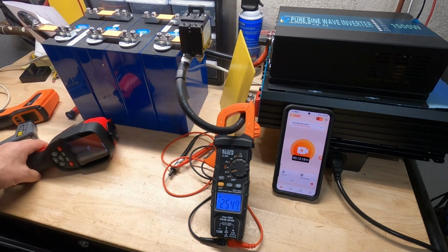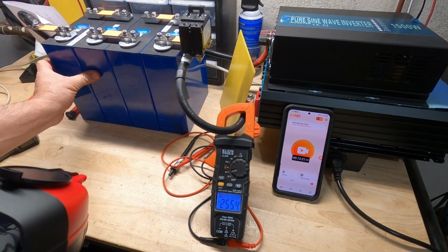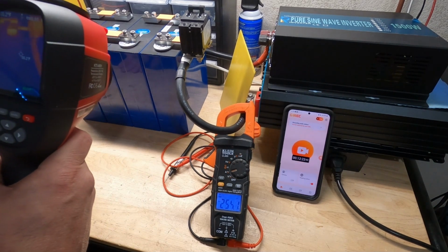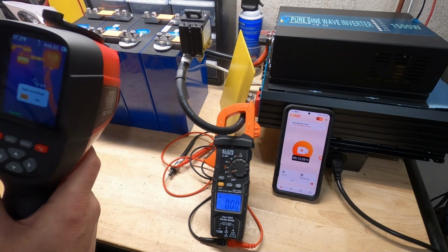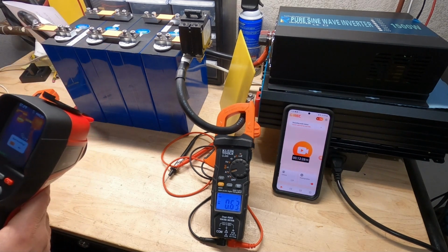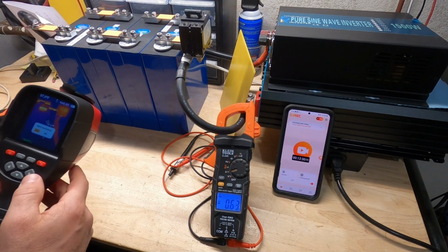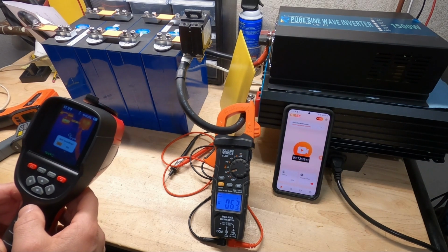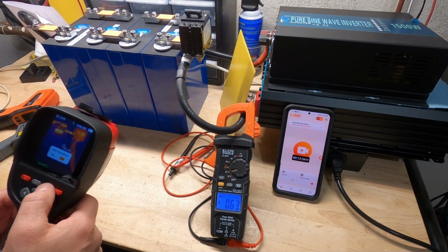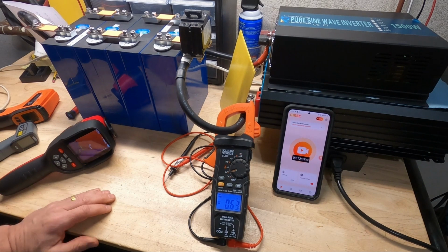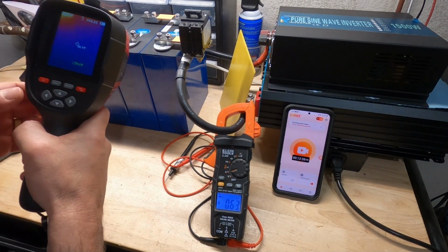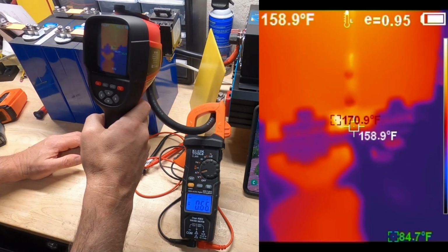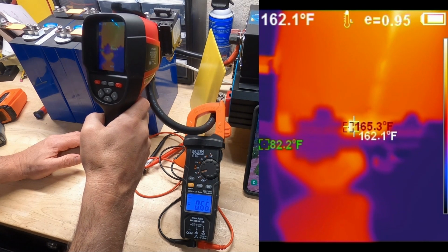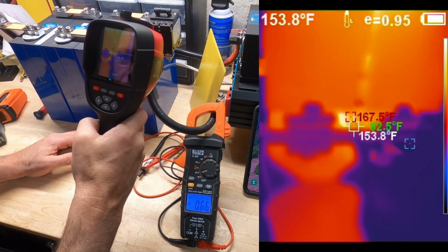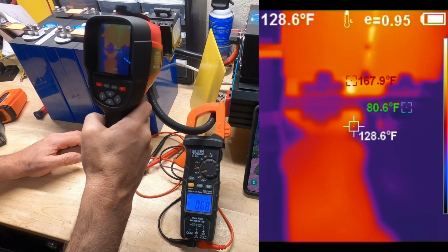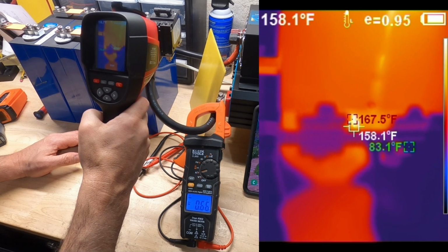This thing's putting out some heat. It's making me nervous, especially them bus bars. There it goes, it tripped. Alright, so we did get a trip on the breaker. So the breaker does function as intended. Alright, that concludes our first test. Let's check the heat. So we'll compare once we take out those metal shims, see if we can't reduce the temps in the breaker.